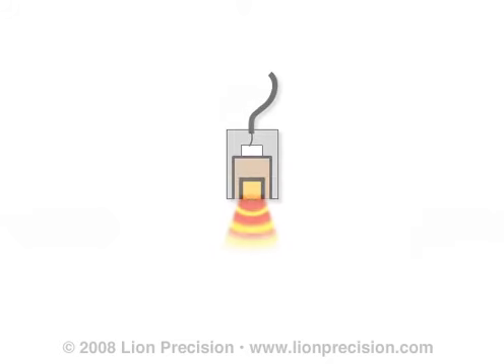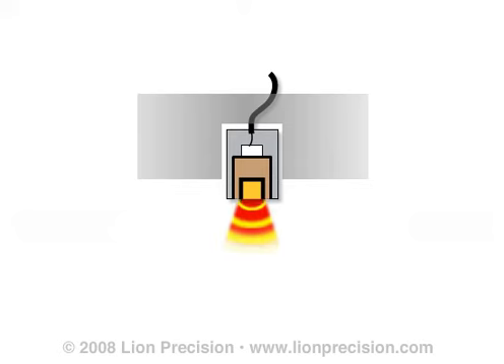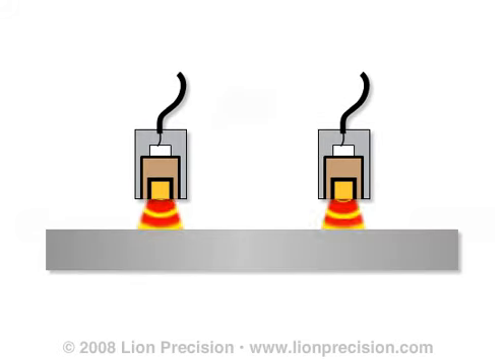The electric fields of capacitive probes are only emitted from the front surface of the probe. The field has a slightly conical shape, resulting in a spot size about 30% larger than the sensing area diameter. Nearby mounting hardware and other objects are rarely in the field area and therefore do not affect the sensor's calibration. When multiple independent capacitive sensors are used with the same target, the electric field from one probe may be trying to add charge to the target, while another sensor is trying to remove charge. This conflicting interaction with the target will create errors in the sensor's outputs. This problem is easily solved by synchronizing the sensors.